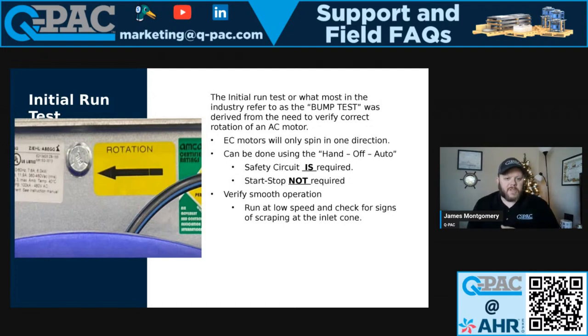Now, for this initial run test, we can use the hand-off-auto switch, and there's a potentiometer on the front of the panel. You've seen pictures of the front of the panel. Put the switch in hand and crank up that potentiometer. You do need to make sure that the safety circuit is made. Say controls hasn't come to help you, or they're not ready to land their wires. At a bare minimum, you're going to need to jump the safety circuit. I talk about those connections. It's between DI1 and 24V.